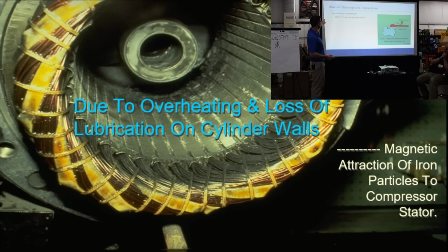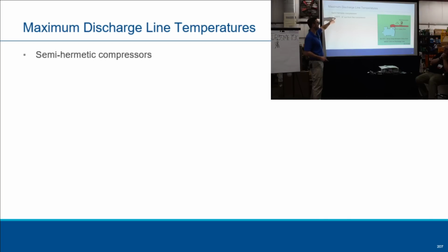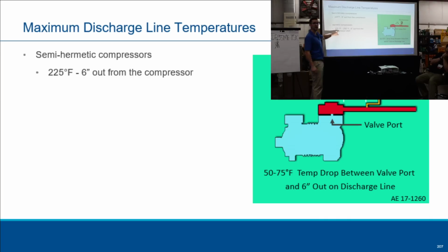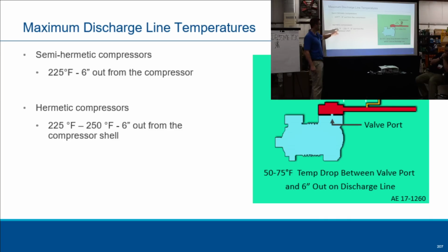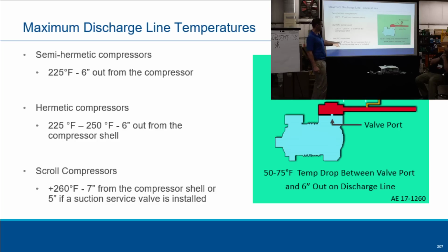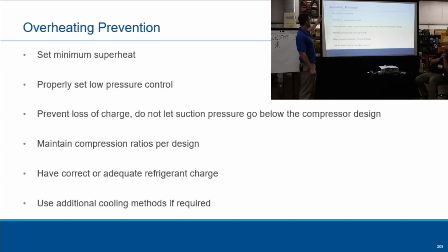Okay, maximum discharge temperatures: 225 on the semi-hermetics. Hermetics, depending on the hermetic compressor, look at the AE Bulletins, it could be 225 or 250. And scrolls, 260, measured 7 inches from the compressor shell, or 5 inches from the suction service valve if it has a suction service valve. Okay, set minimum superheat, properly set low pressure control, prevent loss of charge, maintain compression ratio design, have correct and adequate refrigerant charge, and use an additional cooling method if required.